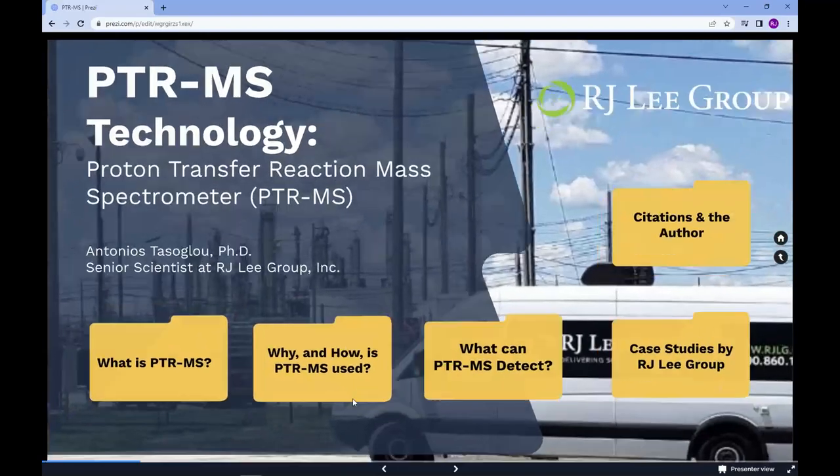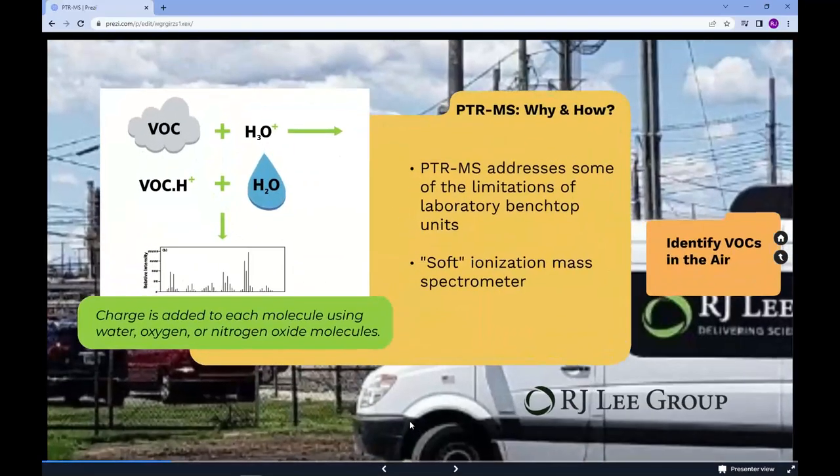The advent of PTRMS technology has addressed several of the limitations of laboratory benchtop units described above. PTRMS is a soft ionization mass spectrometer. Charge is added to each molecule using water, oxygen, or nitrogen oxide molecules, which suppress the fragmentation of the compounds, allowing for a more robust analysis of the mass spectrum.